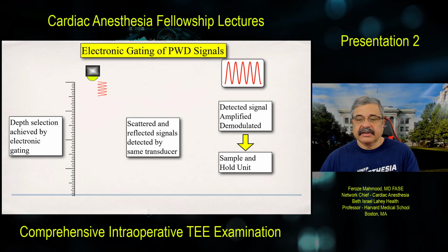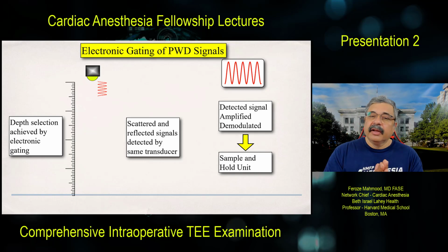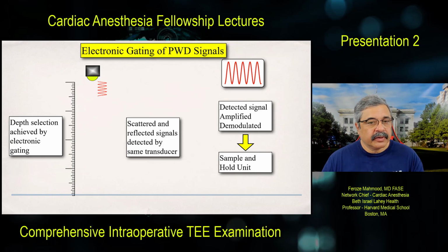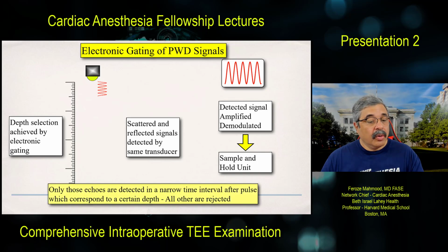The rest of the process of amplification and demodulation is pretty much the same, but this time it's all happening not for the entire line of interrogation, but only at the location of the sample volume. So only those echoes are detected in a narrow time interval after the pulse which correspond to a certain depth. All others are rejected. That's the most important point.